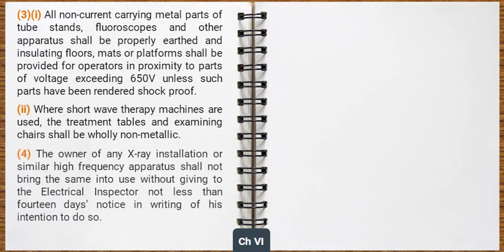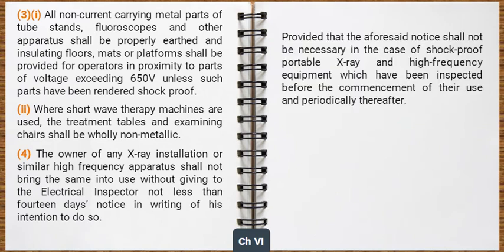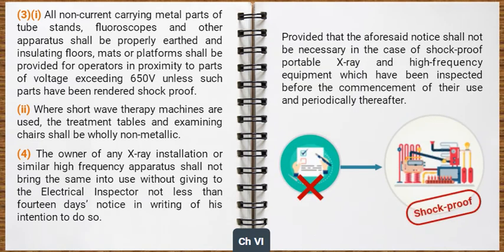The owner of any X-ray installation or similar high-frequency apparatus shall not bring the same into use without giving to the electrical inspector not less than 14 days notice in writing of his intention to do so, provided that the aforesaid notice shall not be necessary in the case of shock-proof portable X-ray and high-frequency equipment which have been inspected before the commencement of their use and periodically thereafter.